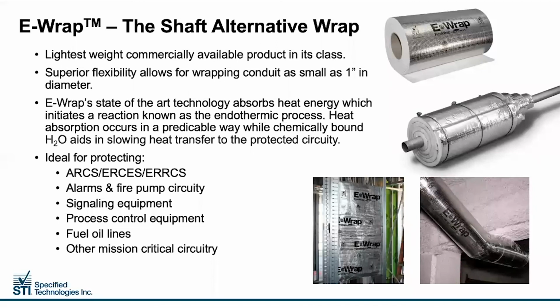As Chris mentioned, one of the considerations RF Solutions must make when outfitting a wireless communication system is pathway survivability. In simple terms, it is the ability for the system hardware to remain operational in the event of a fire. Survivability is perhaps the single most important aspect of an emergency responder system, because honestly, what good is a perfectly designed system without its ability to operate under extreme conditions like those of a building fire?